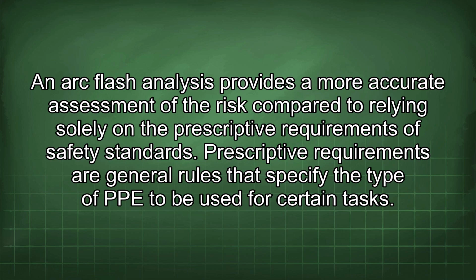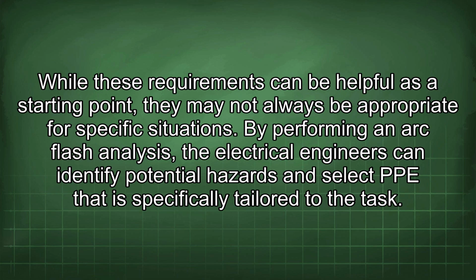An arc flash analysis provides a more accurate assessment of the risk compared to relying solely on the prescriptive requirements of safety standards. Prescriptive requirements are general rules that specify the type of PPE to be used for certain tasks. While these requirements can be helpful as a starting point, they may not always be appropriate for specific situations. By performing an arc flash analysis, the electrical engineers can identify potential hazards and select PPE that is specifically tailored to the task.